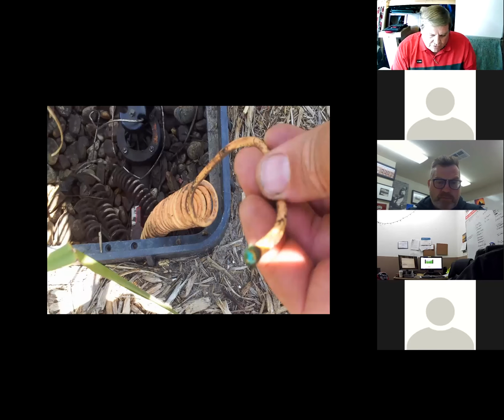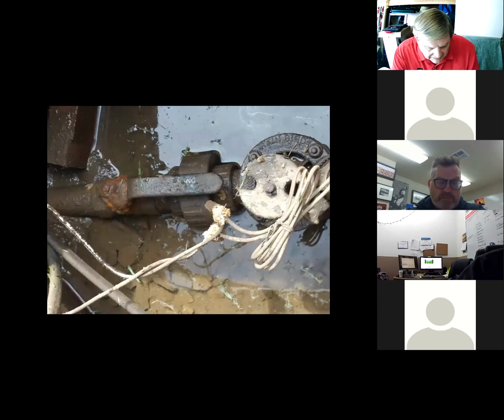Here, the corrosion is so bad the wire just comes right out of the connector. As with this one here, when I grabbed the wire, it came right out of the connector. It's so corroded, the copper is no longer there. Watch for that. Be aware of that. Look at that corrosion there. And this was on a 2-wire system. That much corrosion occurred in, I'm going to say, about 3 to 6 months. It doesn't take long for that much corrosion to occur.